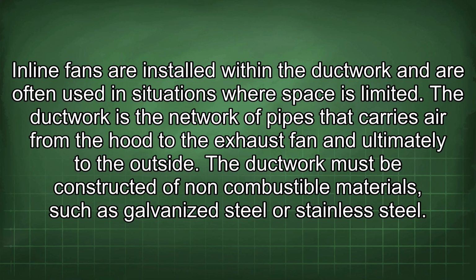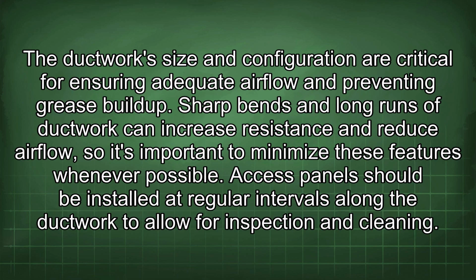The ductwork is the network of pipes that carries air from the hood to the exhaust fan and ultimately to the outside. The ductwork must be constructed of non-combustible materials such as galvanized steel or stainless steel. The ductwork size and configuration are critical for ensuring adequate airflow and preventing grease buildup. Sharp bends and long runs of ductwork can increase resistance and reduce airflow, so it's important to minimize these features whenever possible. Access panels should be installed at regular intervals along the ductwork to allow for inspection and cleaning.